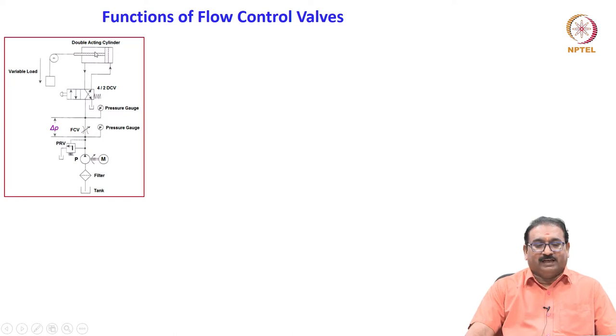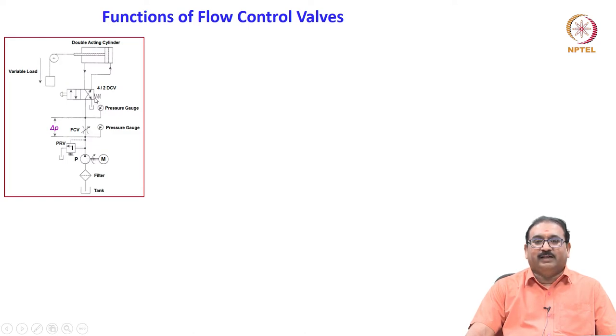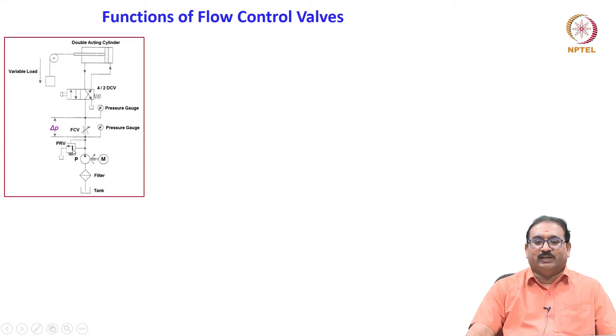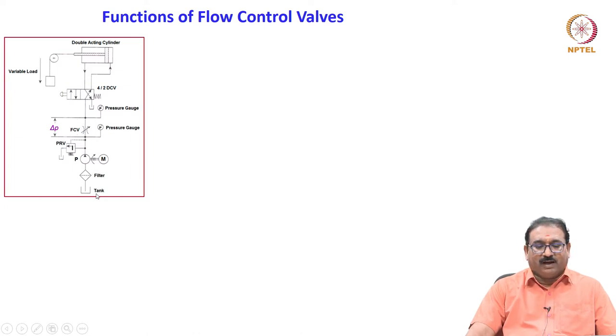Here I am showing a double-acting cylinder used to control a variable load through a 4/2 DCV, spring-centered. One flow control valve is placed between the pump flow and the DCV. This is a throttle type, and a pressure relief valve controls the main system pressure. The pressure gauges monitor the pressure across the flow control valve. There is always a delta P across the FCV; a filter and tank are also shown.